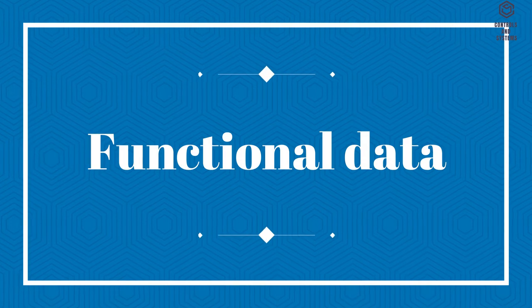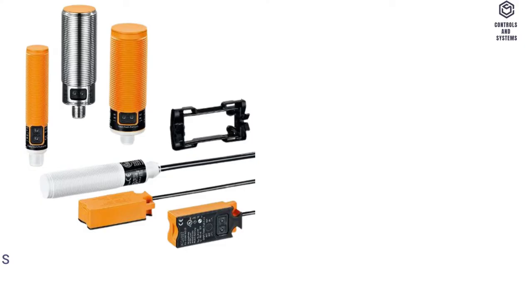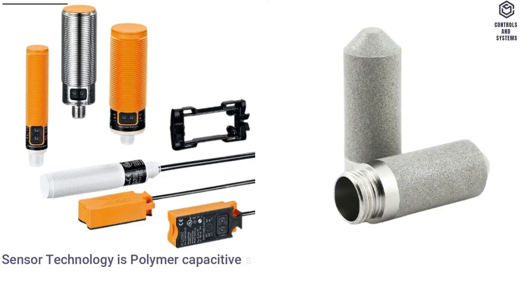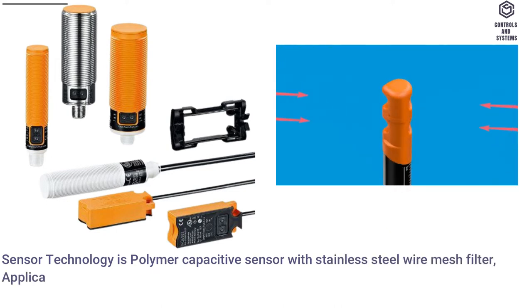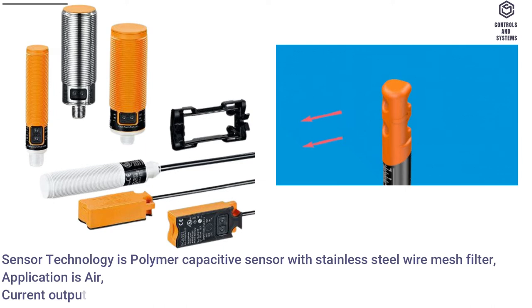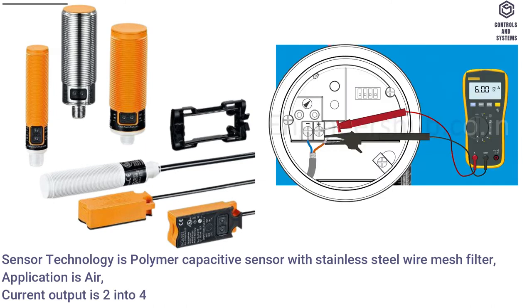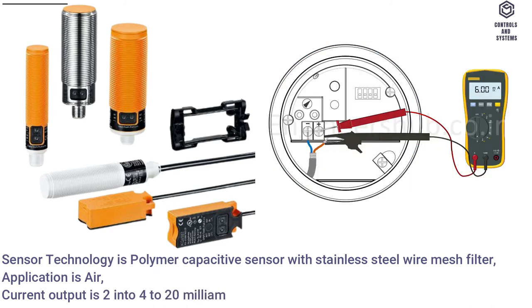Functional Data: Sensor technology is polymer capacitive sensor with stainless steel wire mesh filter. Application is air. Current output is 2× 4 to 20 milliamps. Maximum load is 500 ohm.